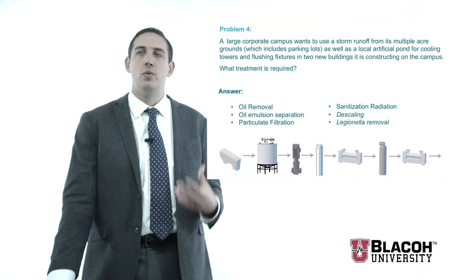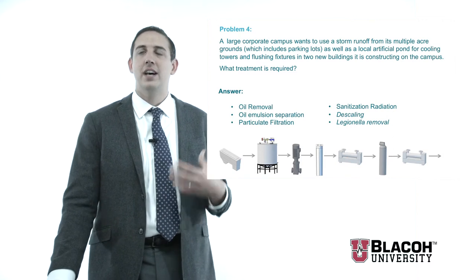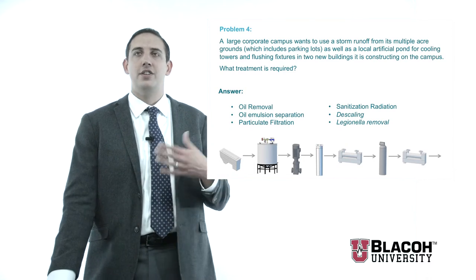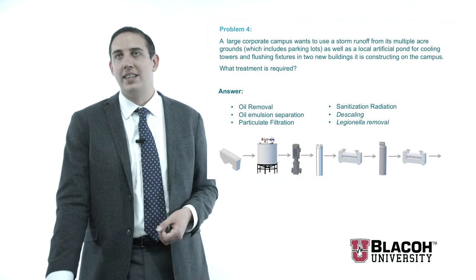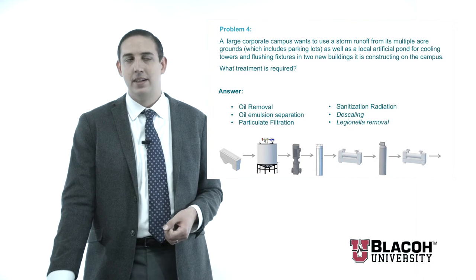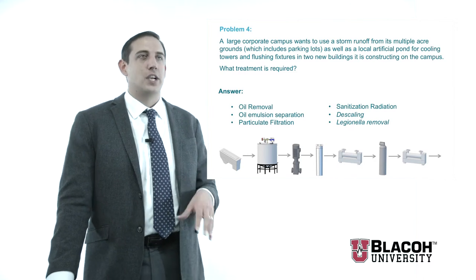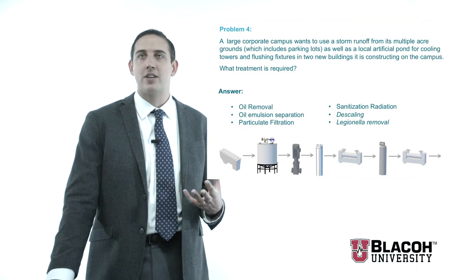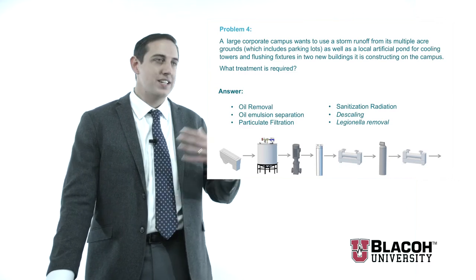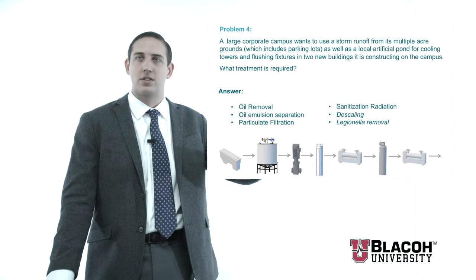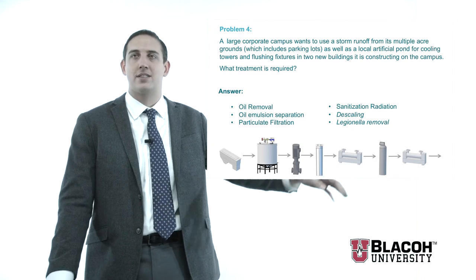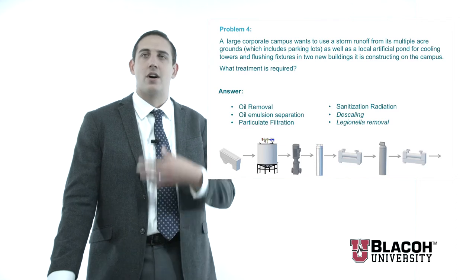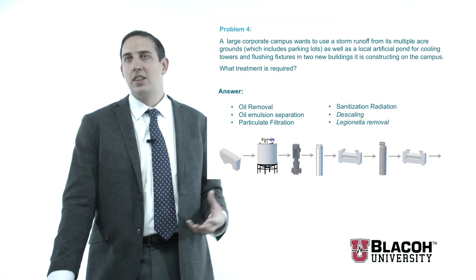However, because this is an outside natural body of water, you do have the potential for Legionella buildup in that tank. From a flushing fixture standpoint, something you would have to monitor as an engineer is whether you have ideal conditions in your transfer loop through your building to generate more and more Legionella. If you were going right to a cistern tank — a big fiberglass vessel — you'd be much like the previous example, using nano filters and ROs and treating the water quite a bit. Utilizing the pond environment kind of helps you out and reduces that treatment burden.